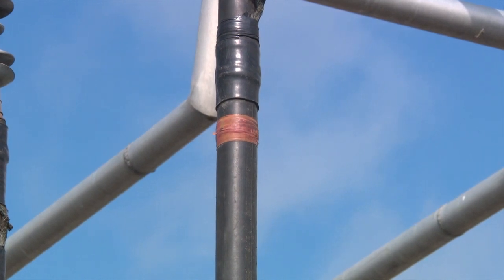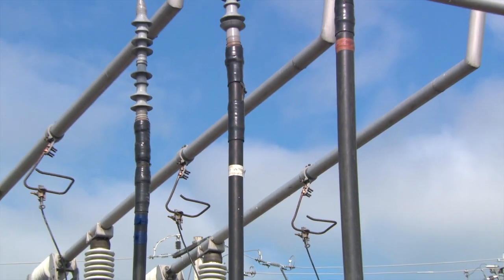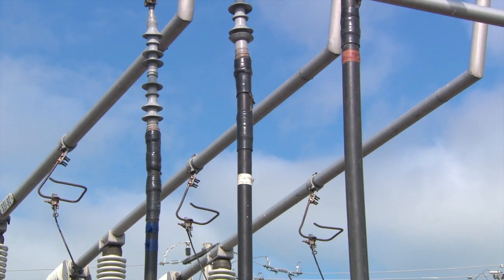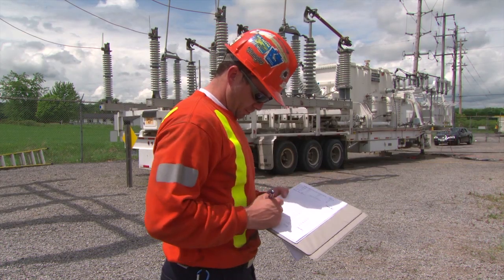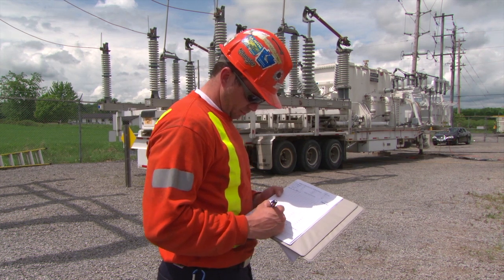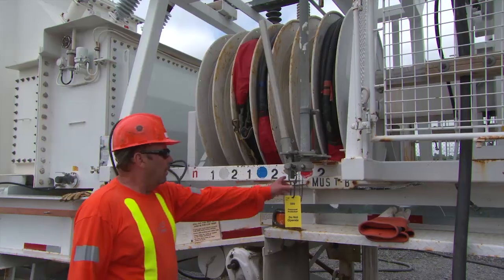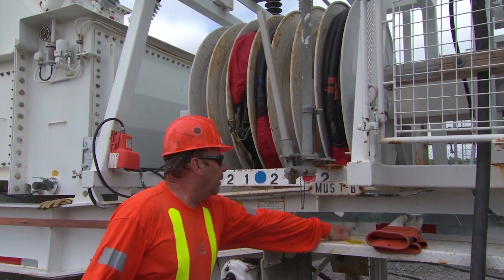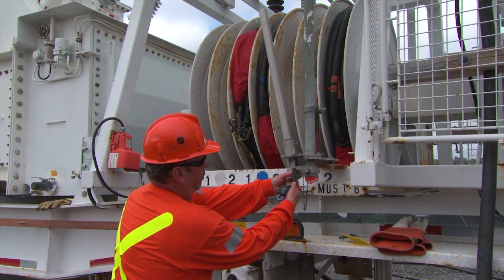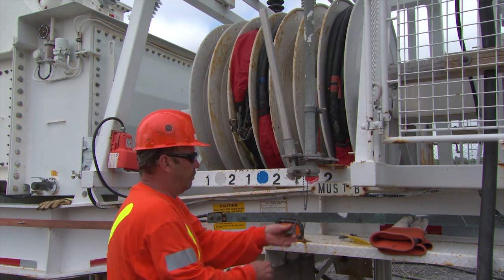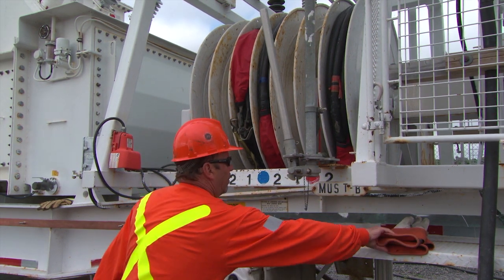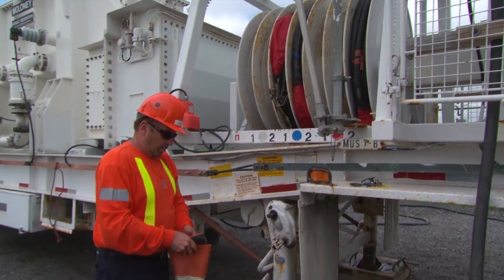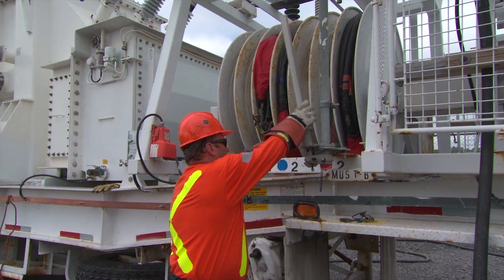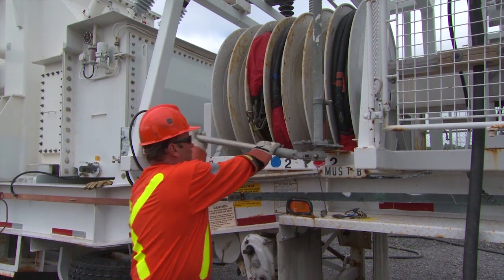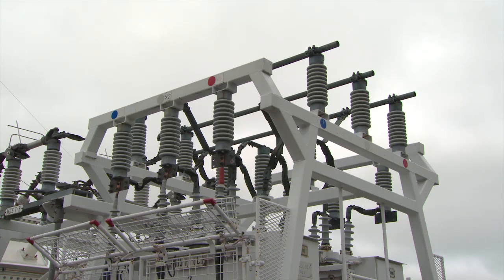After the low-voltage cables are connected, the MUS is ready to be switched into service. Prepare and check an OTO for removing existing work protection tags and switching the MUS into service and the DS out of service. Remove the work protection tag on the low-voltage disconnect switch. Unlock and close the switch and then lock the operating handle in the closed position. Verify the phasing across the opened MUS recloser.